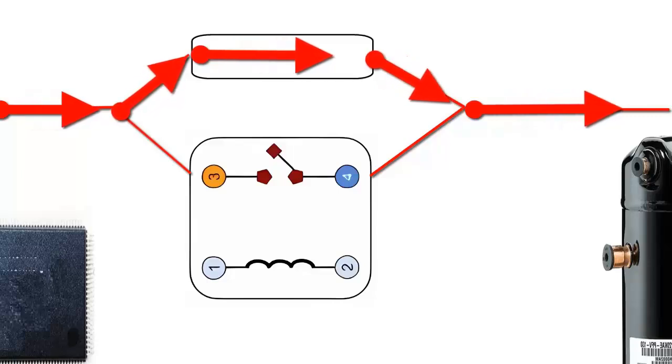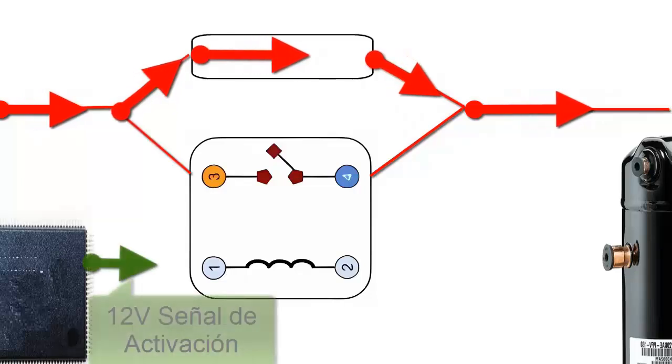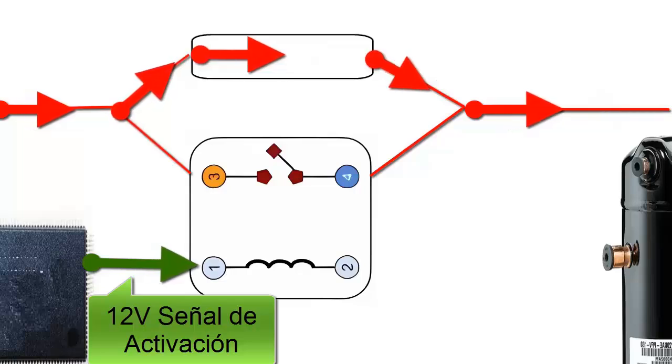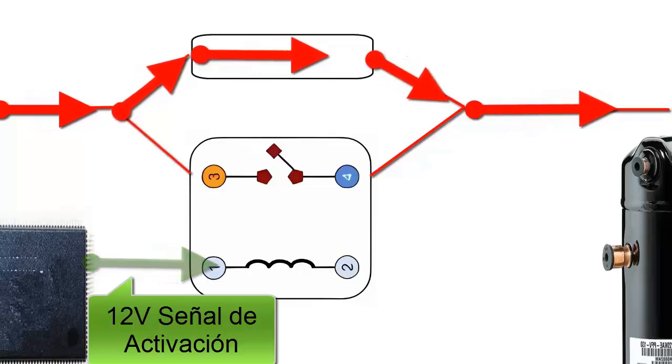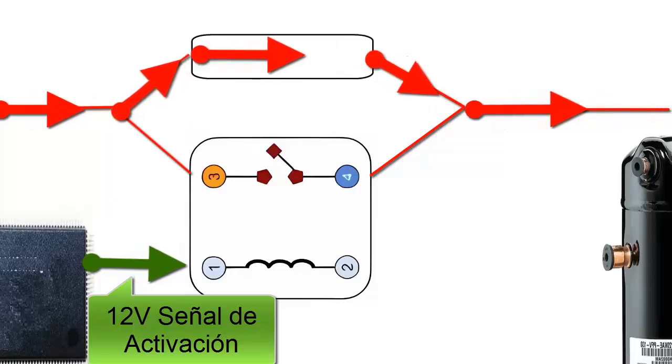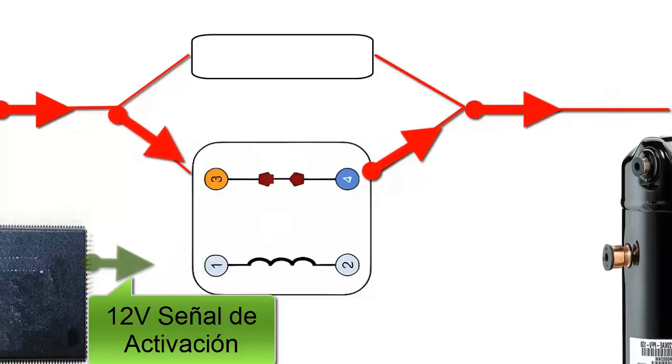Then, upon sensing a normal current consumption, the electronic board's controller sends an activation signal to the main contactor, in this case, 12 volts. The 12-volt activation signal energizes the coil of the main contactor, creating a magnetic field strong enough to close the main contactor switch.